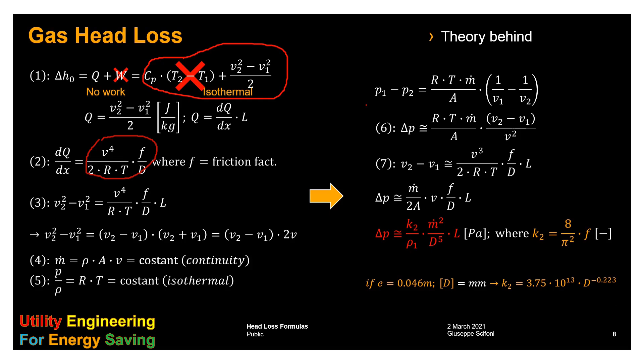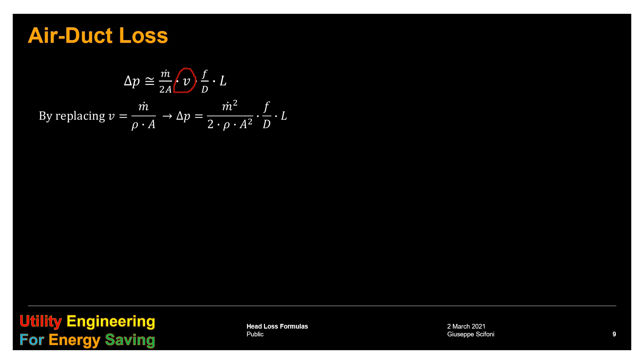For the gas ducts, we need to rework the equation a little bit. And first, we need to change the speed here by using the mass flow divided by density and the area. In this case, the area cannot be expressed as diameter square divided by 4 times pi, because the duct is not always round. And we will introduce here the volumetric flow by replacing the mass flow as density times volumetric flow. And we get this expression.